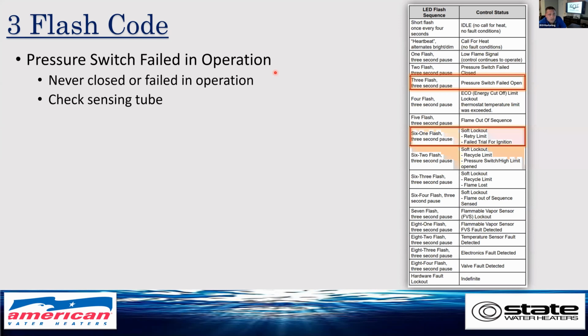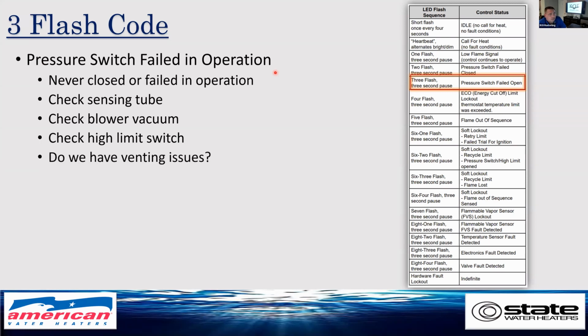One, check that sensing tube, that vacuum hose. That's usually where this code comes from. It's usually on a new install, a 3-flash code, it's torn. So check your blower vacuum. From there, you'll know whether or not you need to check your venting. You could have a blockage in it, or non-supported venting pipe that has now caused a sag. A small blockage could set that high limit switch off as well. So we could be overheating and shutting down in that aspect, because that high limit switch is in the same string that the pressure switch is. So do we have a venting issue? 9 times out of 10, if it's not that sensing tube, there's a venting issue.